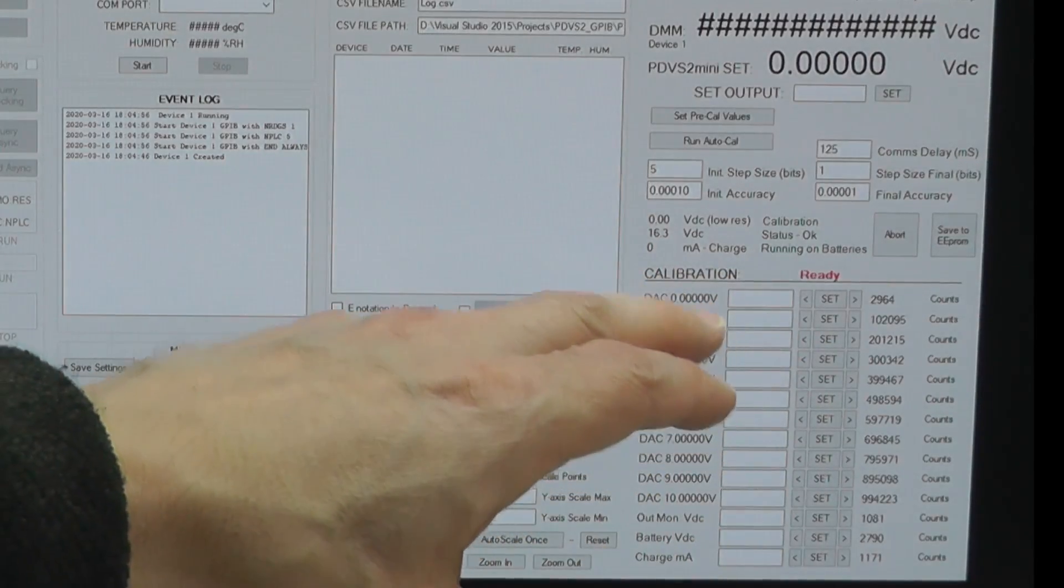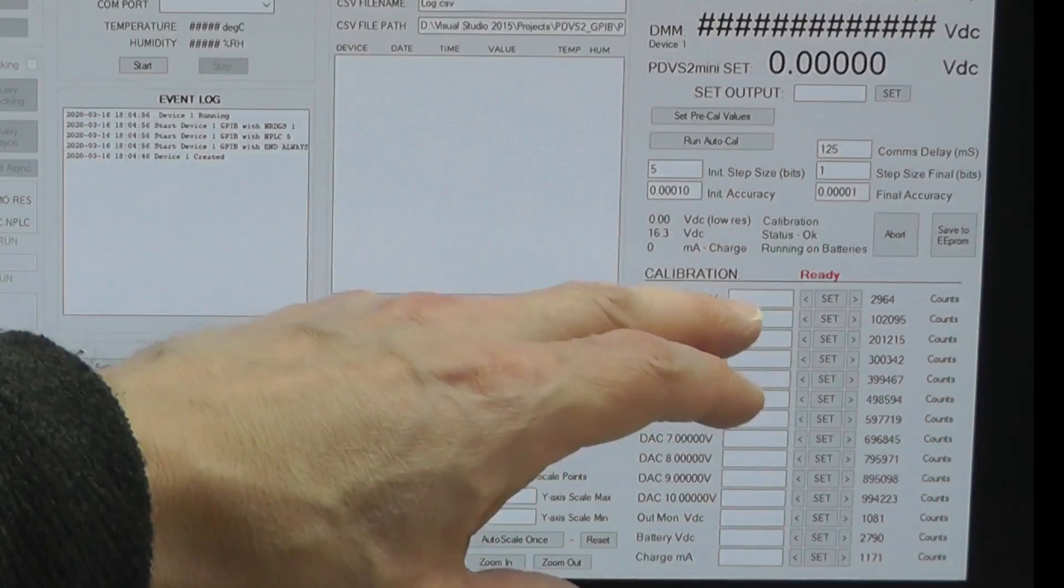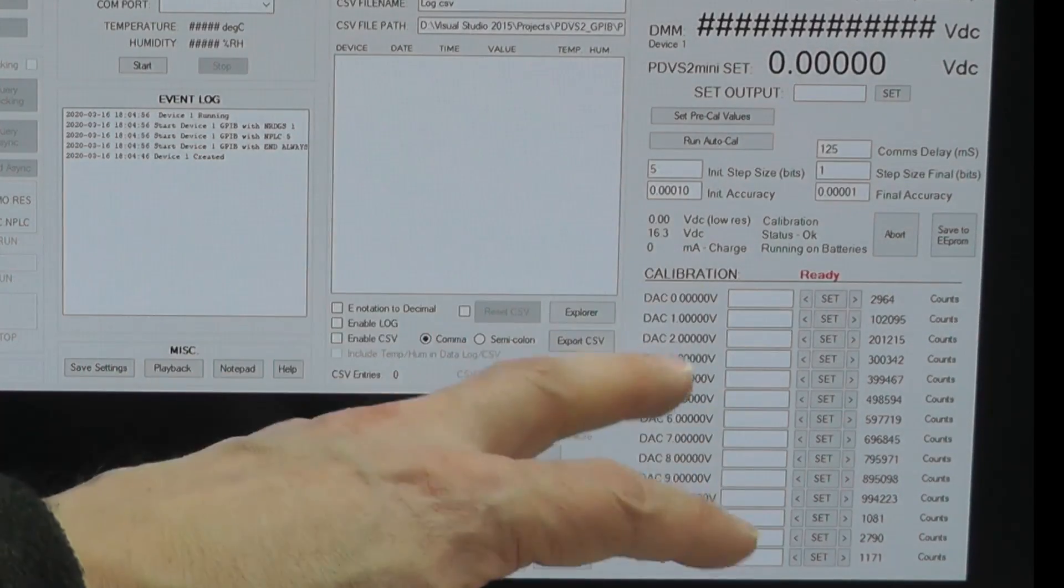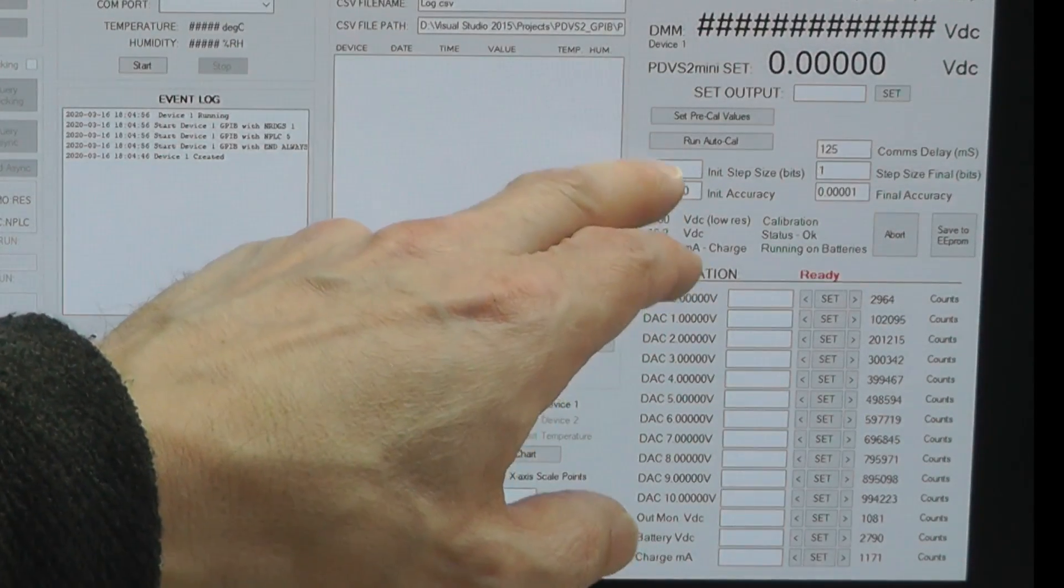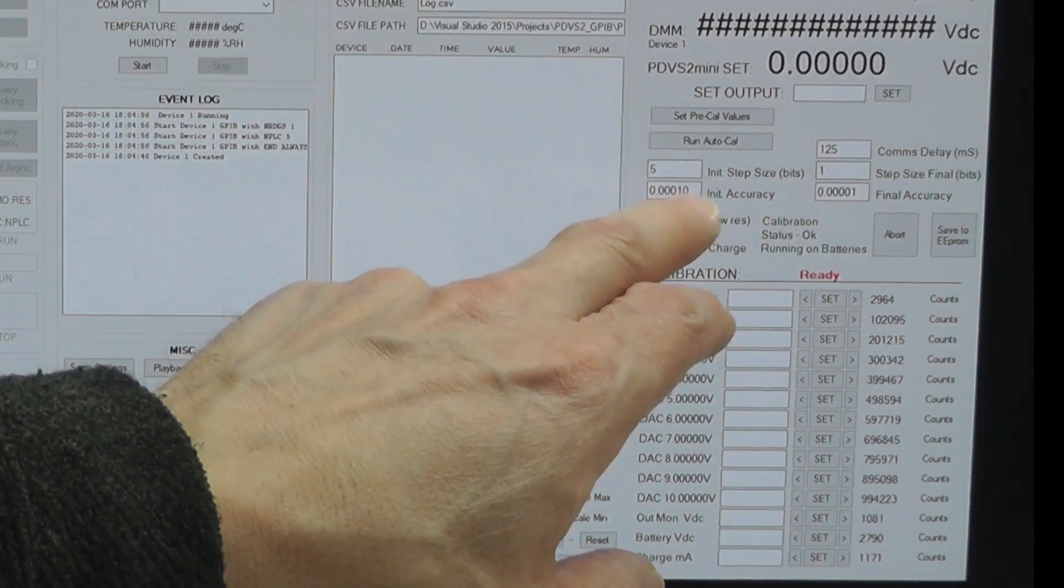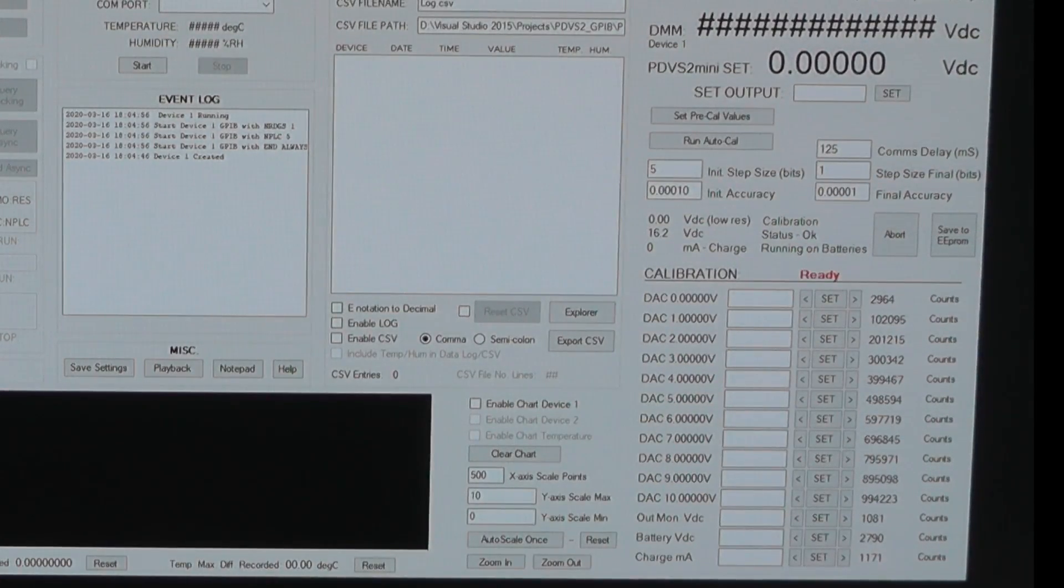...because in actual fact when you run the auto calibration it actually does a first sweep of the first two set points there. And then from the difference between those two it can then go and guess the calibration of the rest. So by doing that you get even closer nominal values before it actually starts the final calibration. And the reason I do that is because the final calibration is done one bit at a time whereas the initial calibration of the first two set points is done five bits at a time so it can get there relatively quickly. Plus when it's running in the pre-calibration it's just looking for an accuracy within 0.0001 and obviously when it's doing the final calibration I want that to 10 microvolts rather than 100.